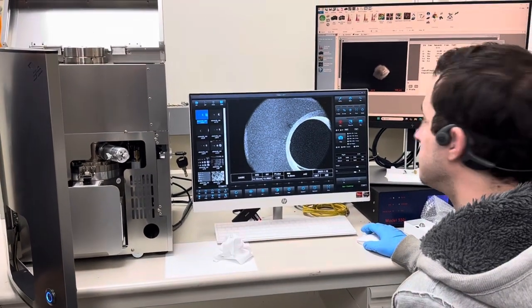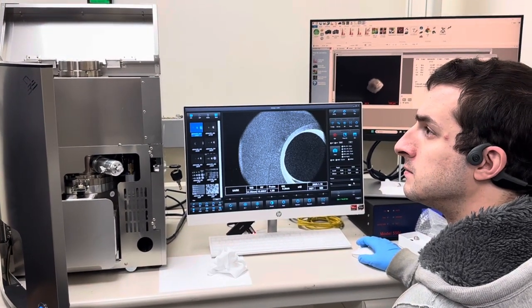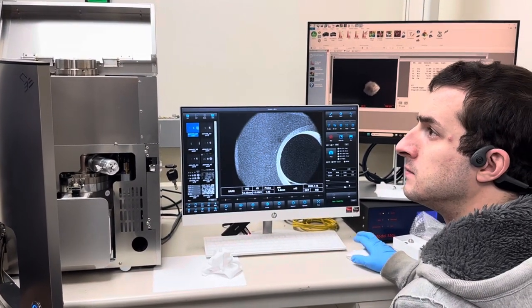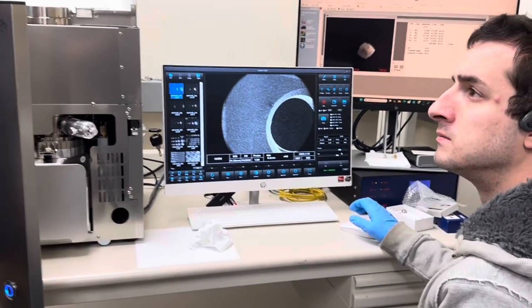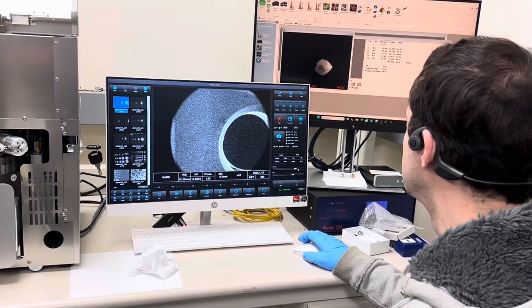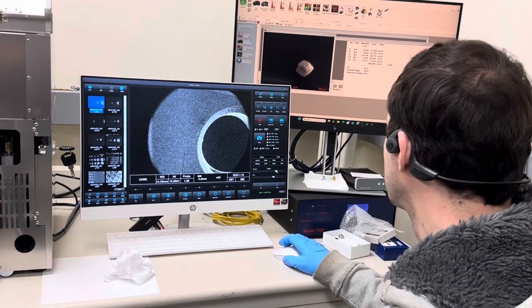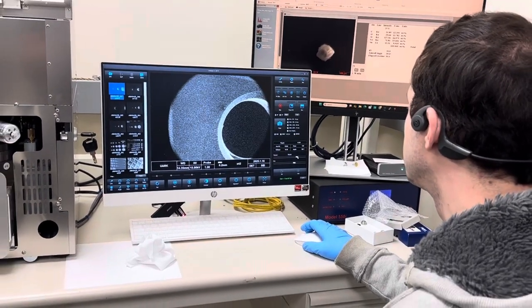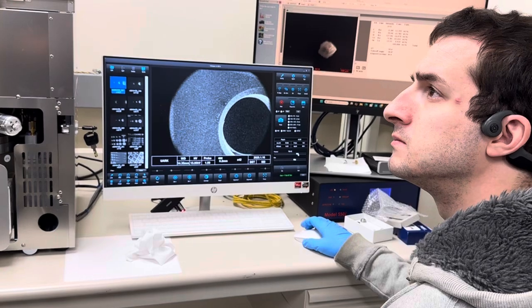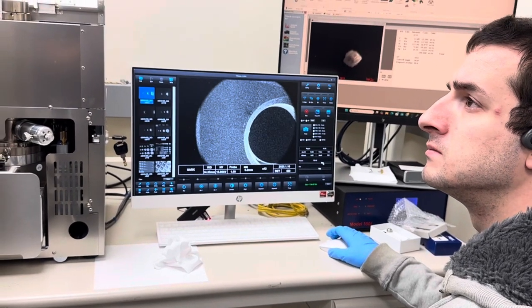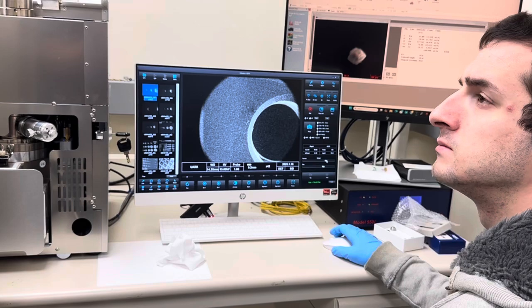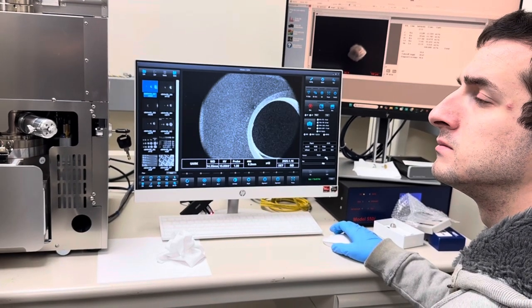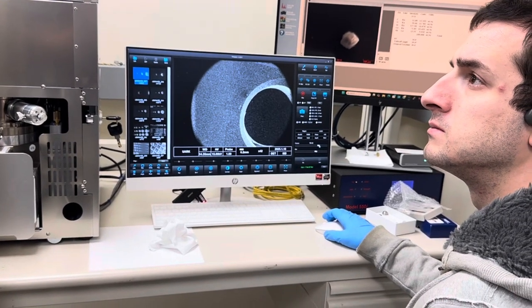Because we're trying to bring voltage up to hit our plateau, to make the maximum voltage with the maximum brightness, right? So right now, if you hover your mouse over that slider, what is it telling us we're at? What number? 732. So that's kind of like an arbitrary number, but sometimes it isn't. Just to let you know, the filaments will saturate very close to their normal numbers. So let's say the filament saturation is 800. Well, it'll be somewhere around 800 all the time.